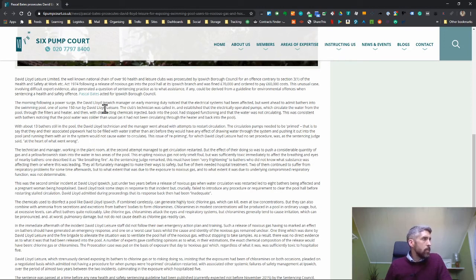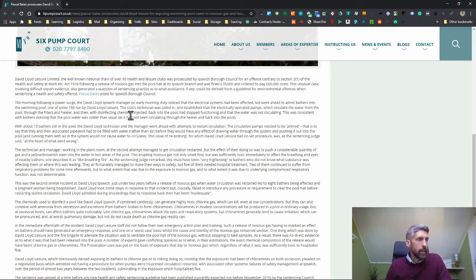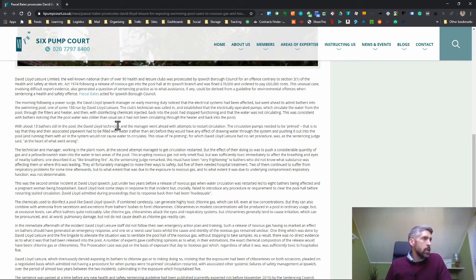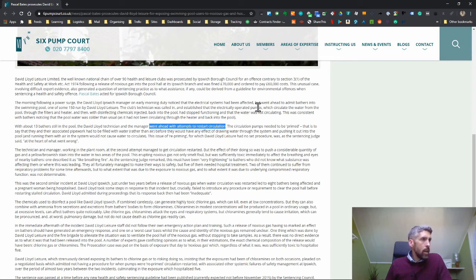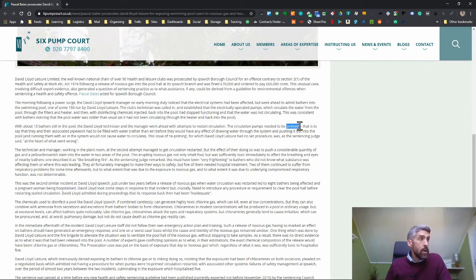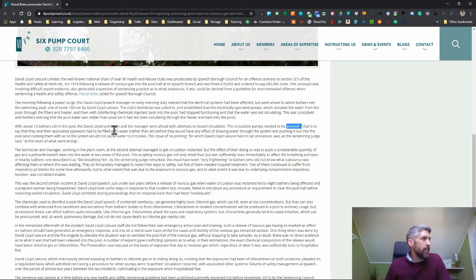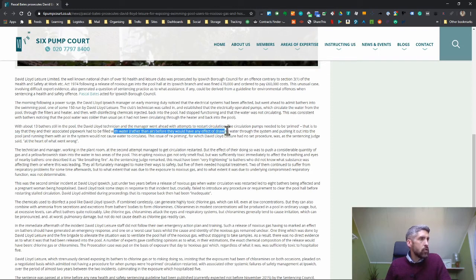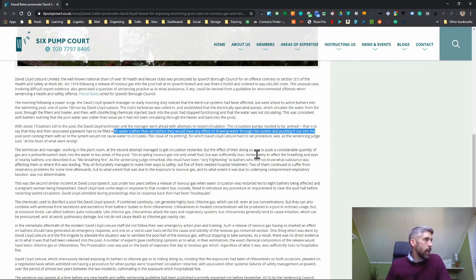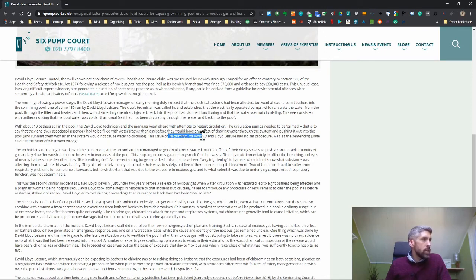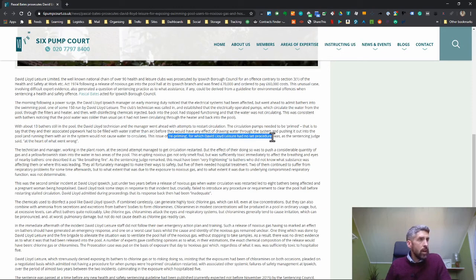This was consistent with bathers noticing that the pool water was colder than usual as it had not been circulating through the heater. With about 13 bathers still in the pool, the David Lloyd technician and manager went ahead with attempts to restart circulation. The circulation pumps needed to be primed because they had lost prime. That is to say that they and their associated pipework had to be filled with water rather than air before they would have any effect of drawing water through the system.